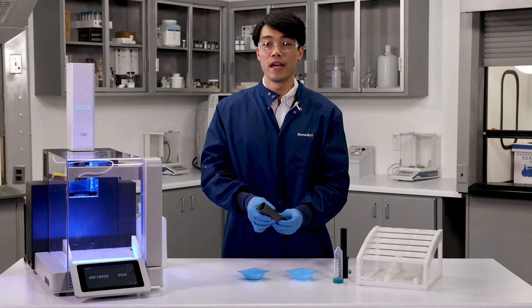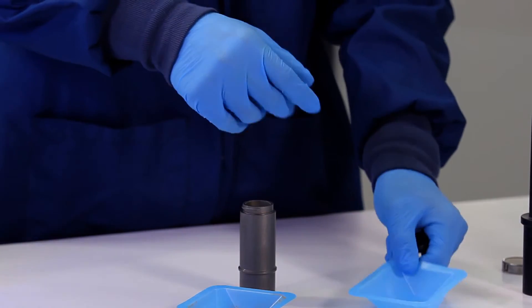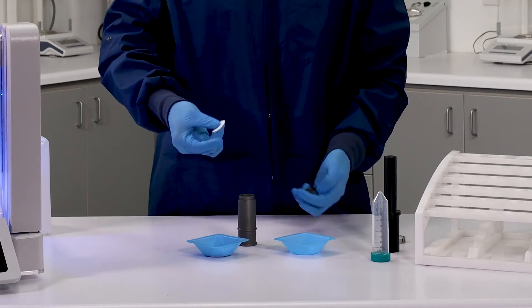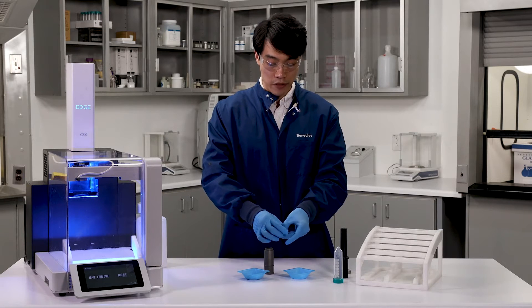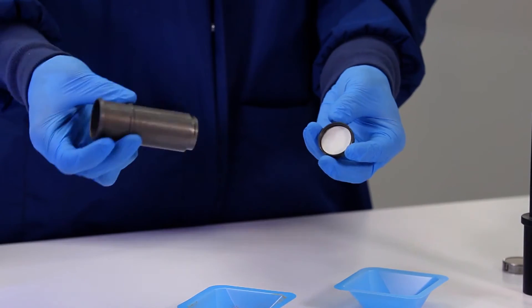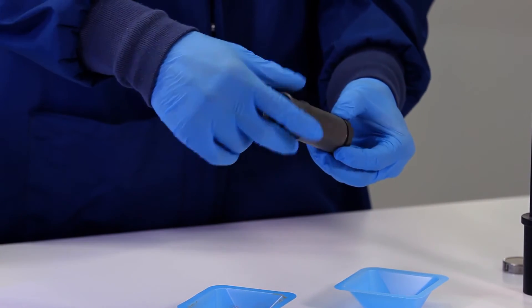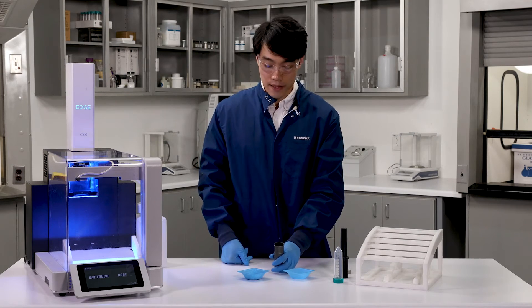So the first thing we're going to do is disassemble our sample cell, and into the bottom, I'll go ahead and insert one of our Q-disks, which acts as our inline filtration for the Edge. I'll make sure it's laying nice and flat around the bottom. I'll take the two components, assemble them together, and then our sample cell has been completed.